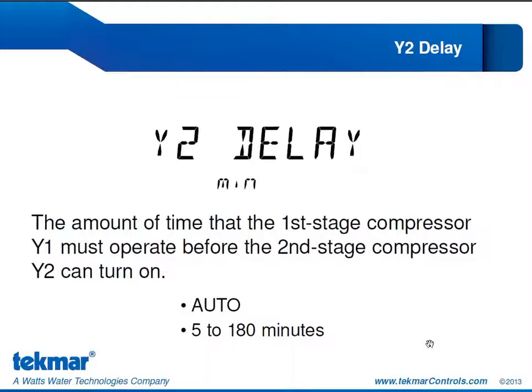Our Y2 delay is the amount of time that the first stage compressor must operate before the second stage compressor can turn on. And similar to W2 relay, the Y2 relay will only close to turn Y2 on if two conditions are met. The first is the Y2 differential has been met, and the second is the Y2 delay time has expired. We can configure this for auto mode, in which there is no additional delay, or for a time ranging from 5 to 180 minutes. So again, we can hold off that Y2 for up to 3 hours if we choose to.